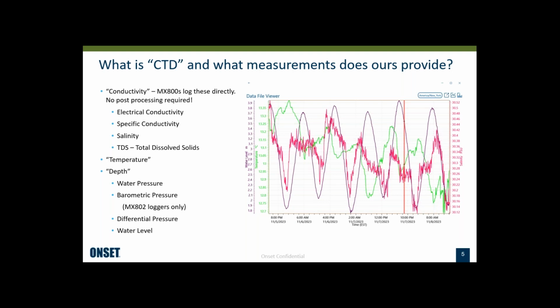Depth really is a combination of measurements. First, we log the water pressure, which is the pressure of the water. You also need barometric pressure, which is included in the MX802 loggers. If you're using an 801, you'll need a separate logger. I'll talk more about that. That provides differential pressure, the difference between those two pressures, which can be used to get water level. So those are the measurements.